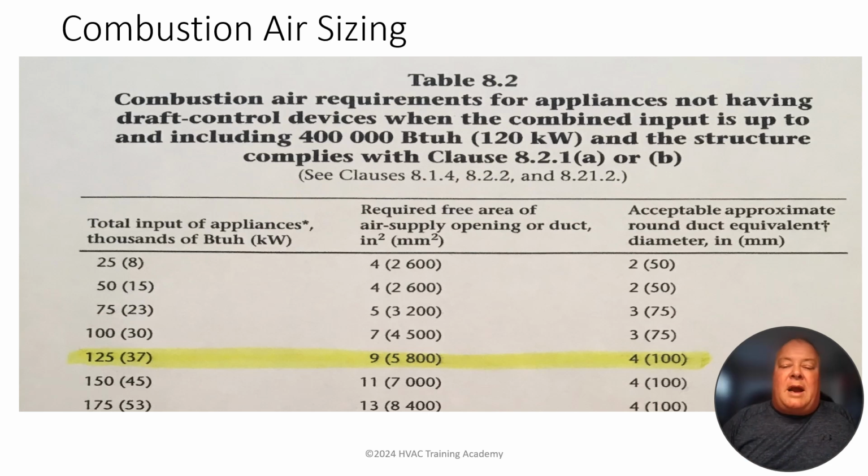The 4-inch round, you might say, okay, well, it was 5 the last time. You're going to find that because of the area of a circle, that number is not going to be half like it was 5 the last time. It's going to be 4 inches now. It's going to be a way different equation. But your square opening will be half as much. And again, that's the one I'd really worry about in this application.